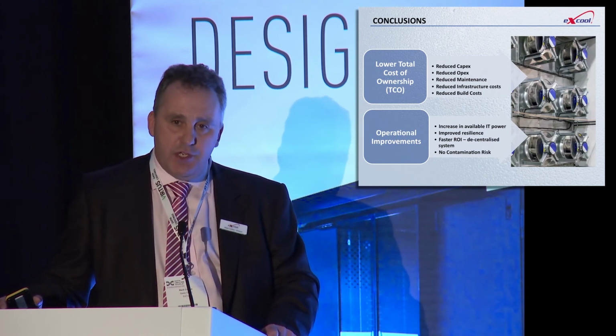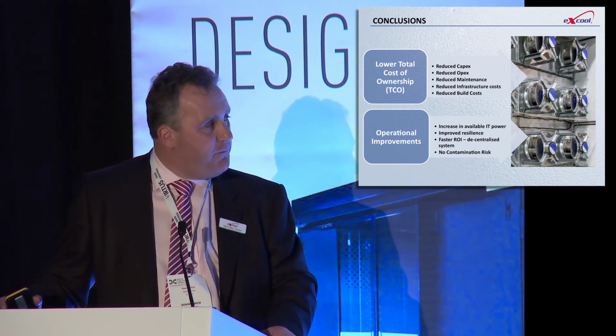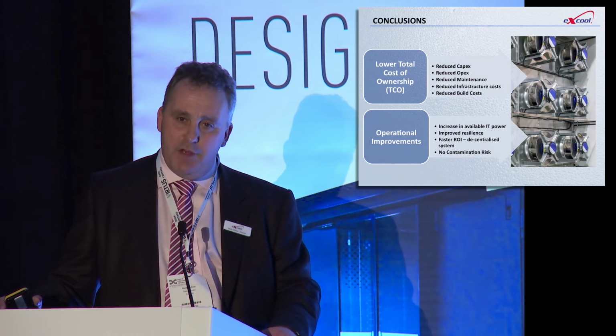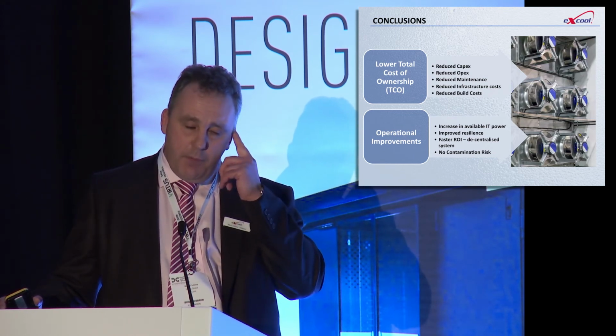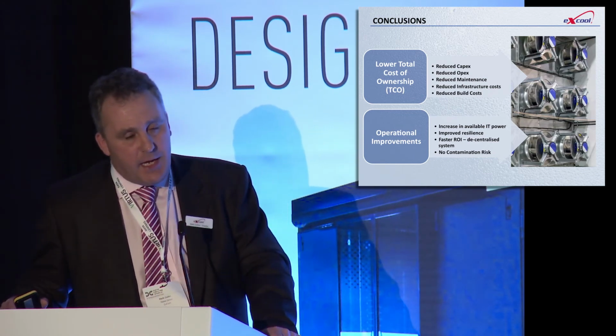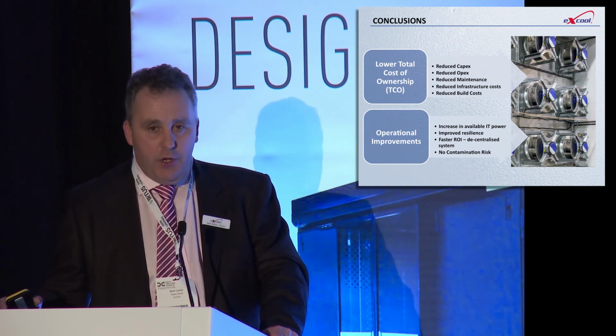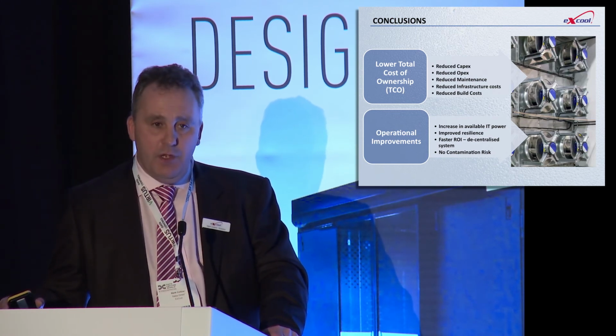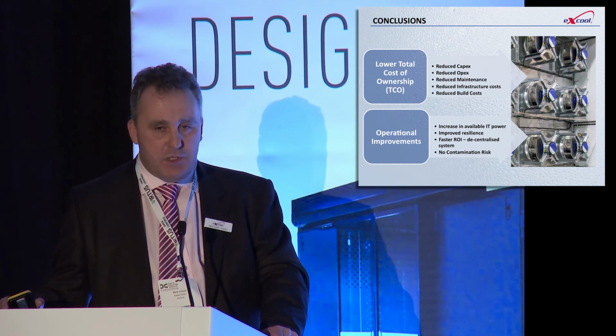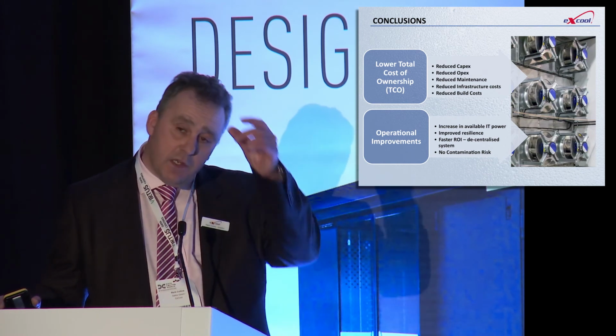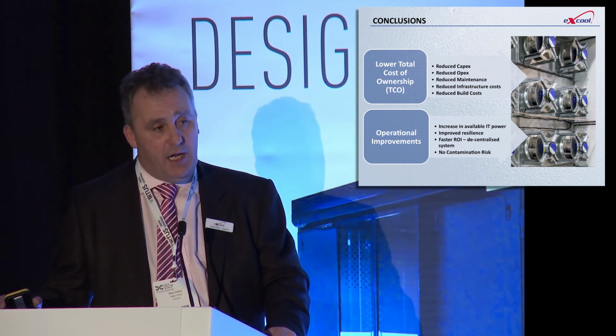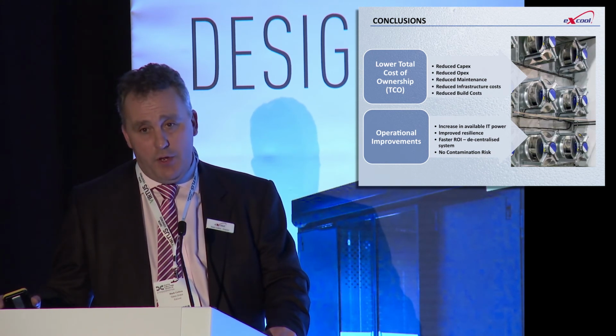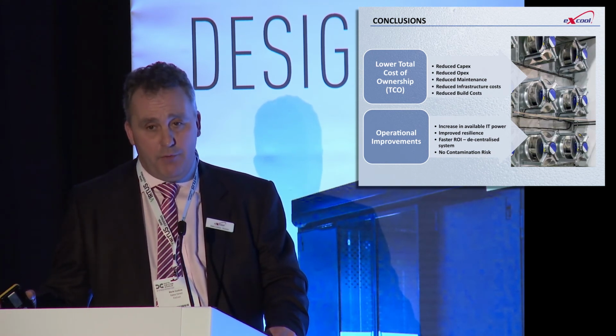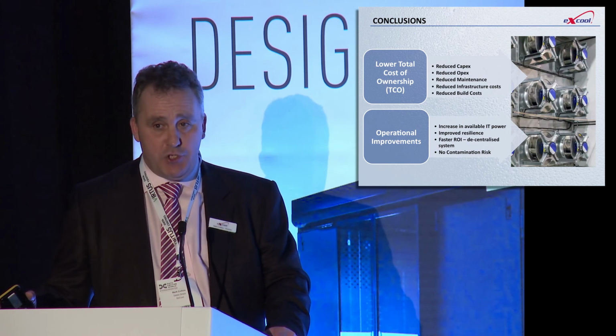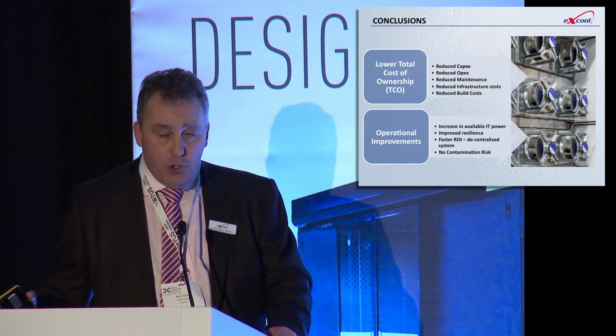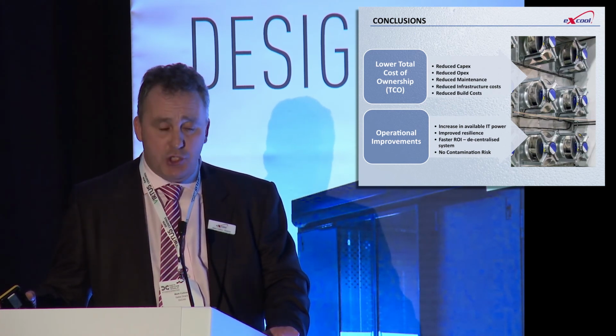We would also get across to you that there's a faster return on investment when you're comparing this with a chilled water system. If you've got a 4 megawatt deployment, let's say, with a chilled water system, you're going to need to put in your chillers, your pipes, your pumps, everything else for that 4 megawatts, and then may only deploy 200 kilowatts of IT to begin with. So you may only put in a small number of CRAC units, but you've got your basic infrastructure in place day one. With Excool, you can install Excool units to match your IT growth.